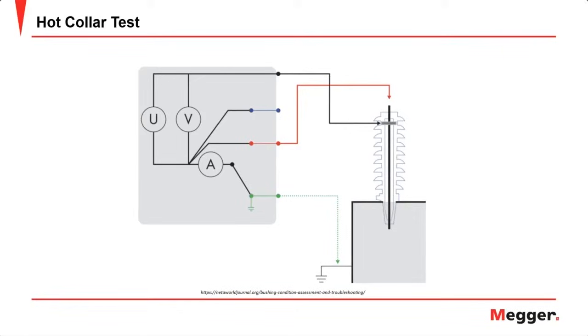And as you see here, with the hot collar strap placed where it is, we can either measure UST R to the red lead, or we can measure GST ground, which would be the red and the green, or we can do GST guard R and just measure the capacitance to ground. So again, it can be very much a diagnostic way of looking at a bushing to try and pinpoint where it may have a failure.